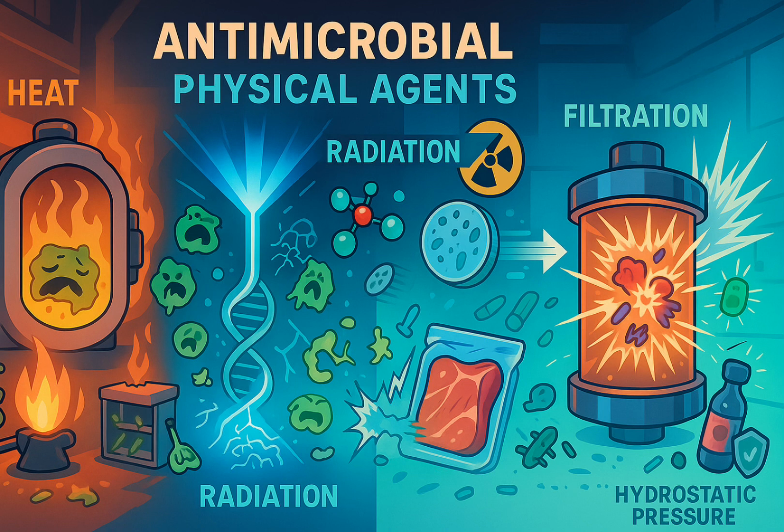And that's why moist heat is generally more effective and faster than dry heat. Exactly. Denaturation is much, much slower without significant water. So dry heat methods need higher temperatures and longer times. Speaking of dry heat, how does that work then? Well, dry heat methods include things like incineration, literally burning infectious waste, and using hot air sterilization ovens. These ovens typically run at temperatures like 160 or even 180 degrees C, but require much longer exposure times than autoclaving, often like 1.5 to 2 hours.